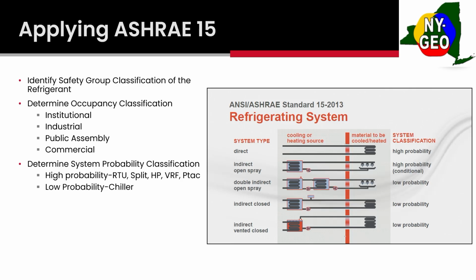A low probability system, the way I look at it, is anything without a fan, like a water source heat pump or a chiller. If there's a leak, it's most likely going to stay in a mechanical room or a machine room where it's not going to get into the occupied space. So those are different factors that we look at when we're designing around ASHRAE 15. For today, we're going to focus on high probability, because that's what we're mostly working with: water heat pumps, VRF systems, split units, and that's where most people are going to be around.